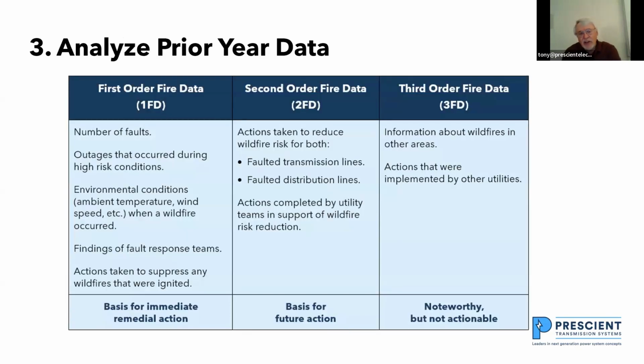And then we have to analyze prior year data. And when I look at prior year data, I'm looking at three classifications: first order, second order, and third order data. The first order is the basis for immediate remedial action. If I have 1,000 faults in a 1 month period, that's like, wow, tremendous amount of things I have to change. So I want to know how many faults are occurring and how many outages are occurring during high risk conditions. And who's evaluating the environmental conditions, the ambient temperature, wind speed, and things like that. And what's the findings of the fault response teams?